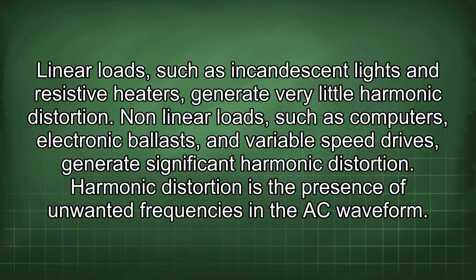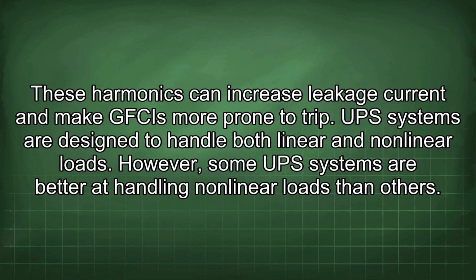Linear loads, such as incandescent lights and resistive heaters, generate very little harmonic distortion. Non-linear loads, such as computers, electronic ballasts, and variable speed drives, generate significant harmonic distortion. Harmonic distortion is the presence of unwanted frequencies in the AC waveform. These harmonics can increase leakage current and make GFCIs more prone to trip.